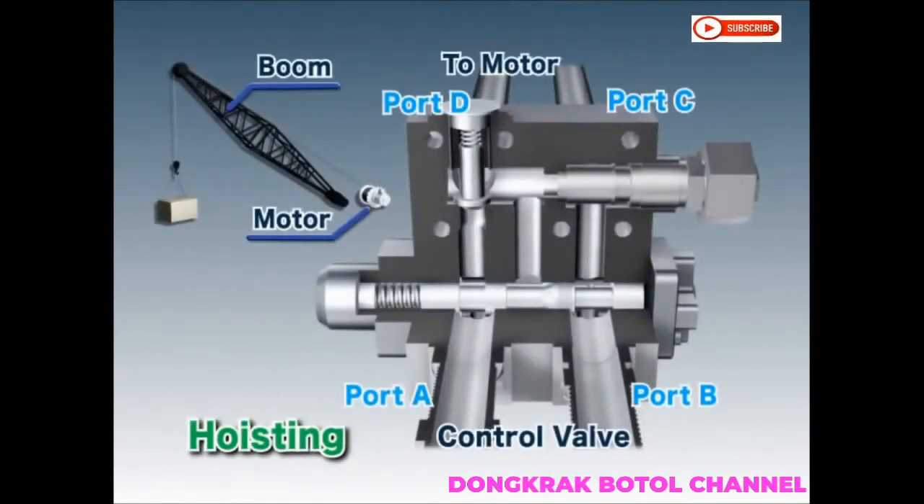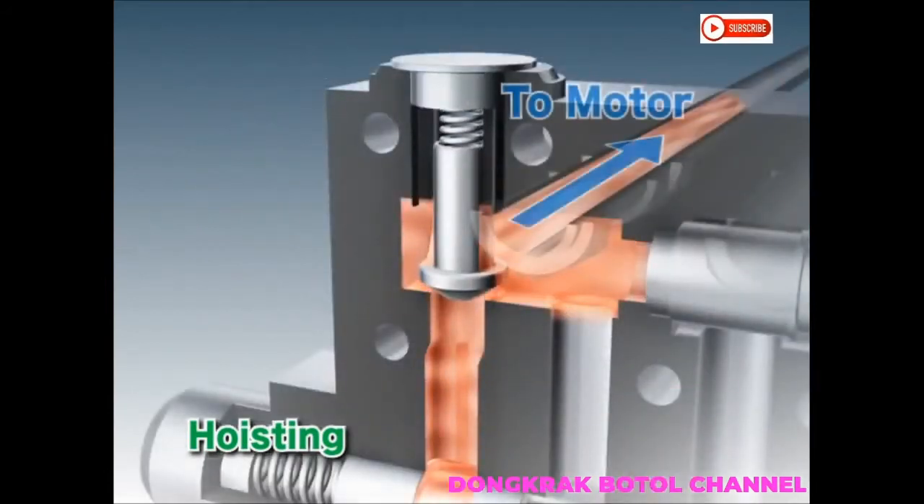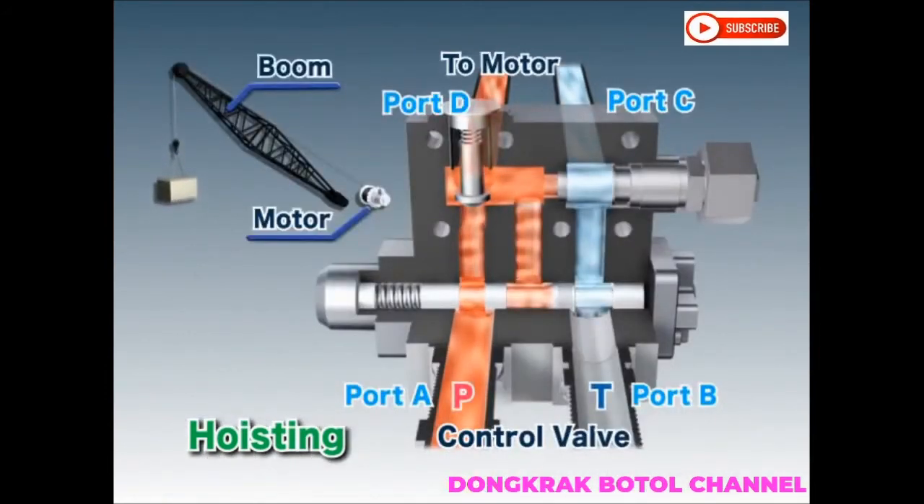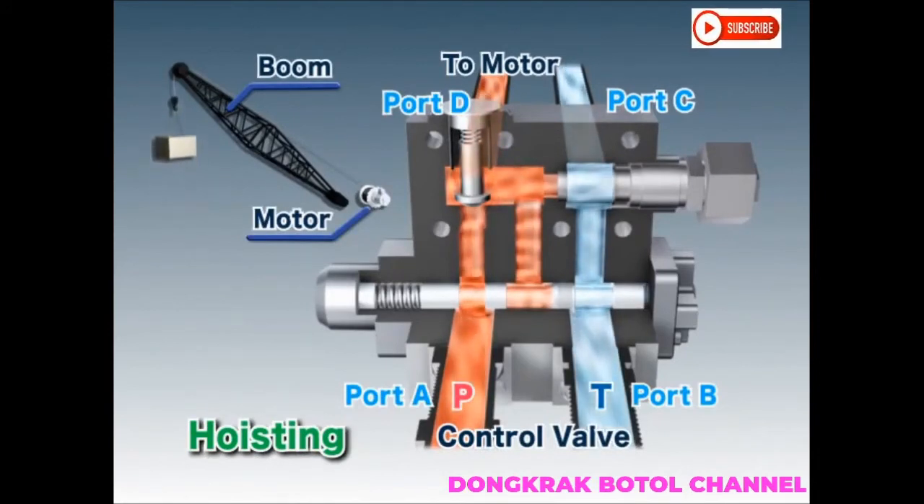When a load is being lifted, hydraulic oil from the pump passes through port A, pushes open the poppet on the check valve, exits through port D towards the motor, and rotates the motor. The returning oil from the motor then passes through ports C and B and returns to the tank.